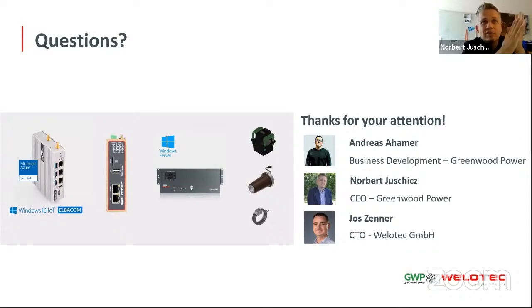Yeah, you will fail if you install a voltage sensor with only class 1 and you have a device with additional 2-3% inaccuracy and an additional inaccuracy by cables and input impedance. So we have 5% inaccuracy. Then this use case makes no sense anymore. So this must be considered during the first discussions. Then you can set up on top of this solution some kind of these algorithms.